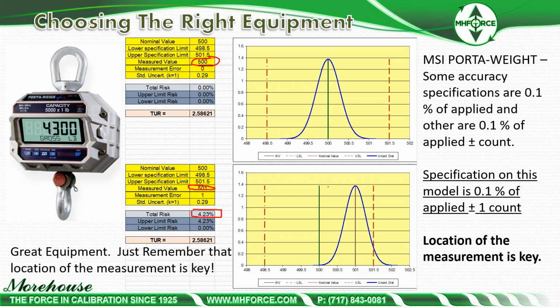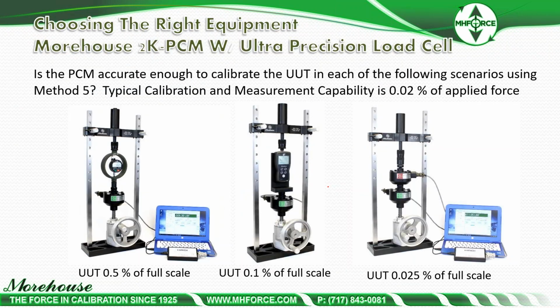Like I said, if it shifts at all, it is tough to make the statement of compliance. You can look at this as a PCM. This is a piece of equipment whose primary purpose is to eliminate hand weights. A lot of people stack weights on these handheld force gauges, which ergonomically produces a big safety hazard. So this machine was created to allow a portable set to do handheld force gauges, digital force gauges, load cell to load cell.